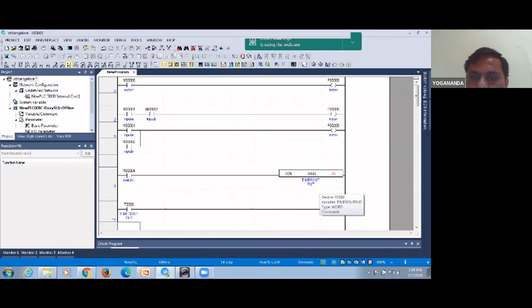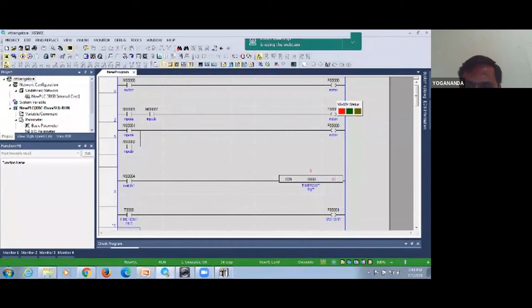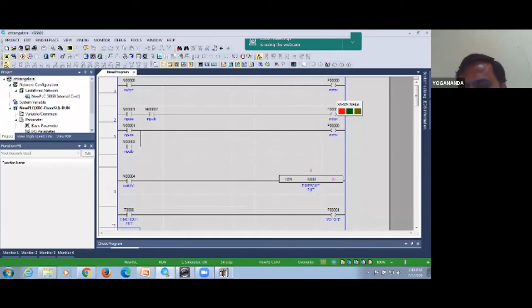So now save that ladder diagram and then go for start simulator. Then you can see now. Okay. Now if this switch is on, the timer is going to start counting its value up to 20. After that particular time that we have initialized in the on timer, after completion of that, the timer output is going to send the signal to this switch, then only the motor is going to turn on. That is my objective, or that is my aim.